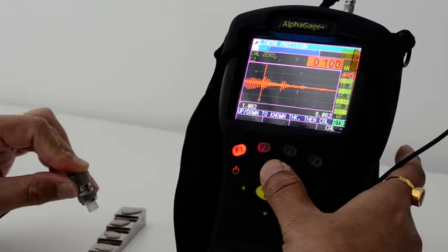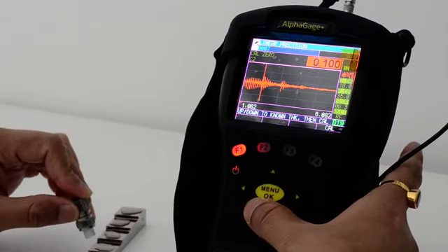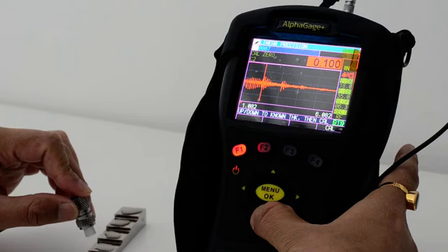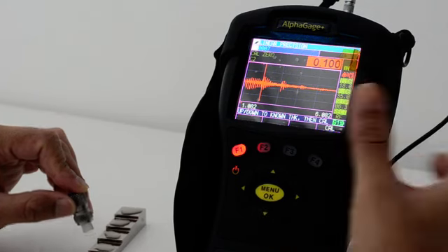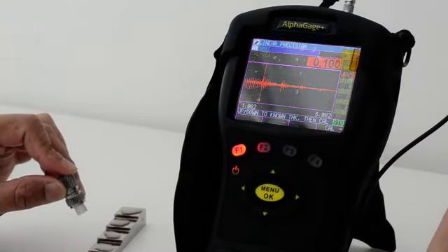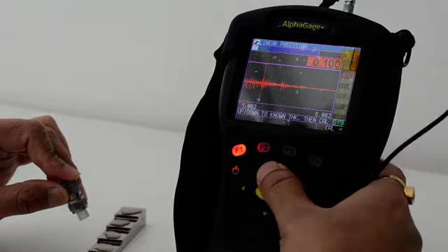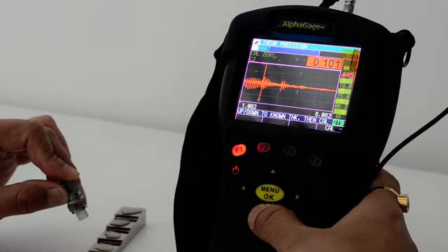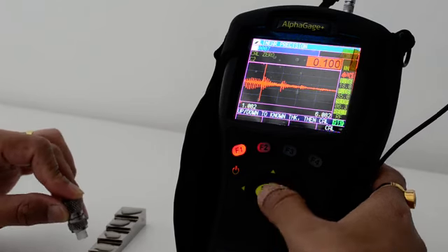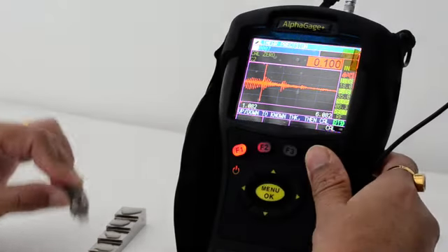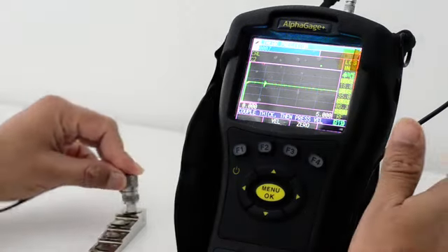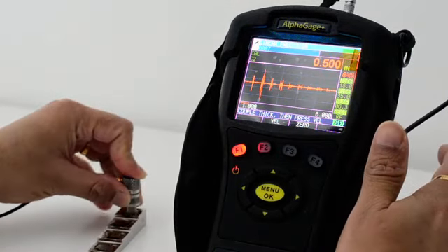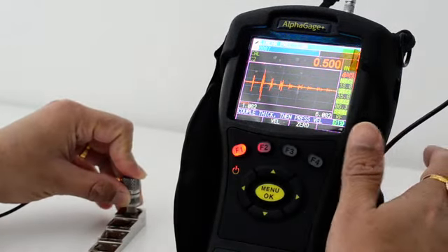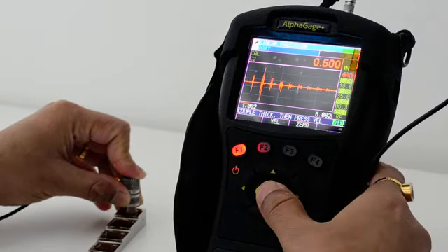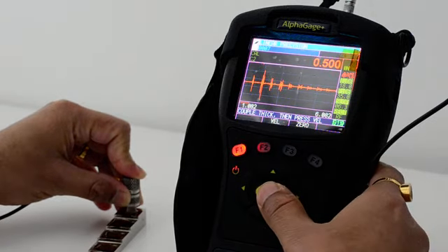and since I know that this thickness is 0.100 inches, if it is not coming as 0.100 inches, then I'll change it and bring it to 0.100 inches, and then I'll press cal. And I'll go to the thick standard, and the thick standard is 0.500 inches. So once I get this, I press OK.